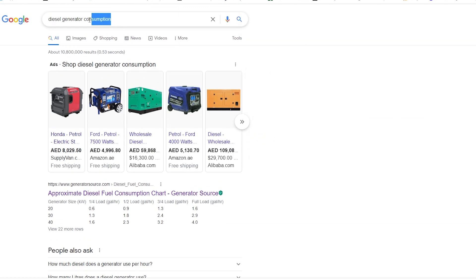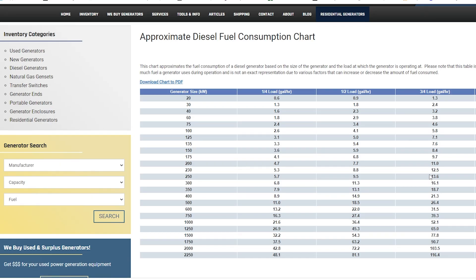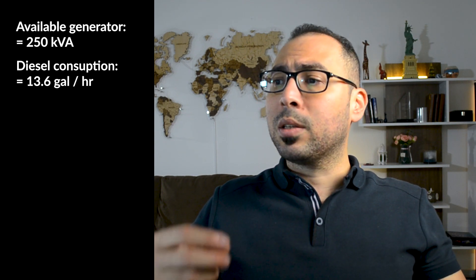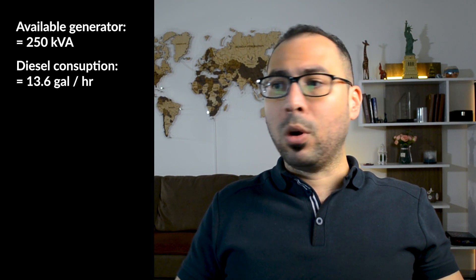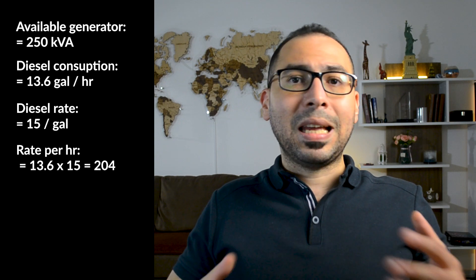For fuel consumption, you can search online for diesel generator fuel consumption charts showing all capacities and consumption in liters or gallons per hour at 25%, 50%, 75%, and 100% load. I'll assume the generator runs at 75% load. For a 250 kVA generator, that's about 13.6 gallons per hour. If the diesel rate is 15 per gallon, the hourly consumption cost is 13.6 times 15, which equals 204.